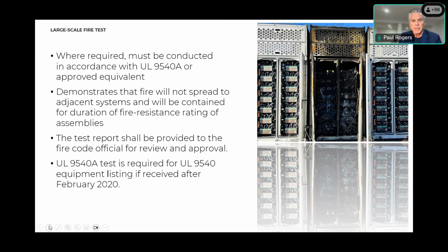It's important to know this is a data collection test, and there's a lot of different things that come out of it that help validate the installation itself, and things associated with the installation and the battery system, with deflagration control and heat release rates and other data that can be utilized by the code official or the peer review to validate information needed to make sure this system will not have any interaction outside the system itself. So we can move on to the next slide.